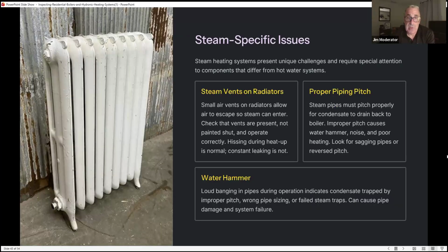Steam specific issues. On these steam systems, steam vents on radiators, small air vents on radiators, allow air to escape so steam can enter. Check the valves, check that the vents are present, not painted shut, and operating correctly. Hissing during heat up is normal, consistent leaking is not.